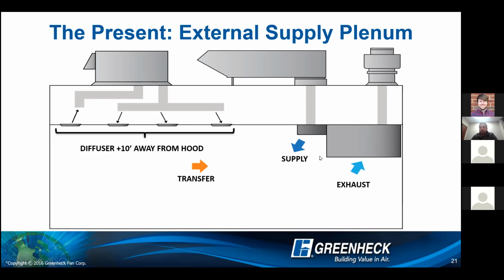This air is going to create a curtain. This is not a technical term, but it's typically not going to be creature comfort air, so it's not going to be dehumidified. The non-technical term I use is, I like to think of it as cutting the air. So you're typically just going to cut that air to get it down to a leaving air temperature of around 70 degrees. And then you're going to bring that lightly conditioned air into the space. It's not going to be dehumidified. So it's not a perfect solution, but at least it's not super expensive air because this provides an air supply curtain. Most of that air is going to be quickly exhausted.